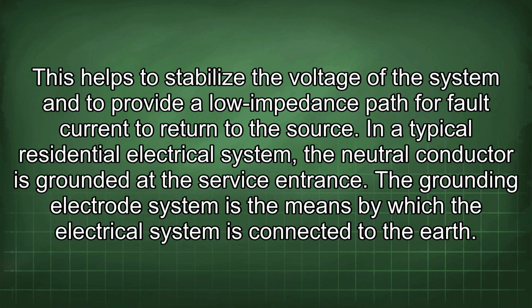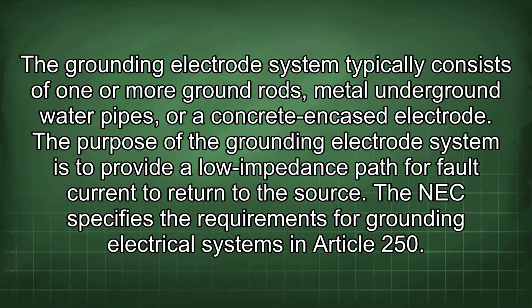The grounding electrode system is the means by which the electrical system is connected to the earth. The grounding electrode system typically consists of one or more ground rods, metal underground water pipes, or a concrete encased electrode. The purpose of the grounding electrode system is to provide a low impedance path for fault current to return to the source.